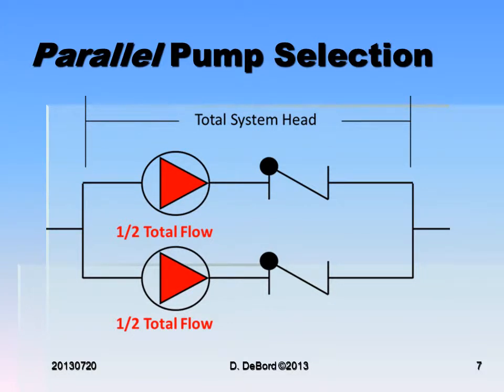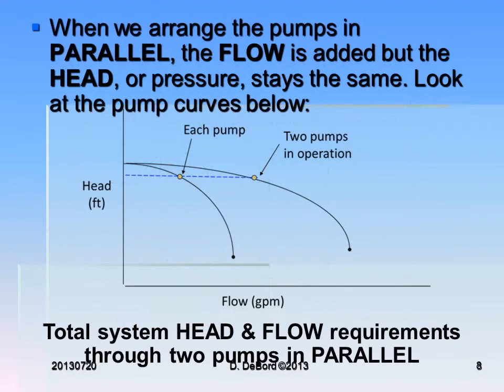Parallel pump selection looks like this. We see the total system head, but half the flow is through one pump and half the flow is through the other pump. When we arrange the pumps in parallel, the flow is added but the head or pressure stays the same. Each pump curve shows about half the GPM of the total of the two, but the head is the same whether you have one or two pumps in operation. So with two pumps operating in parallel, the flow is multiplied but the head is the same.